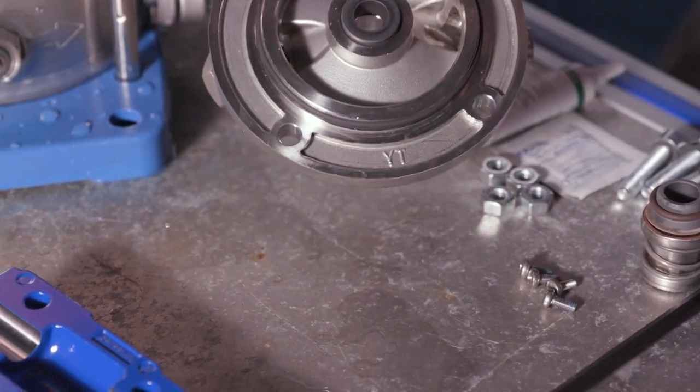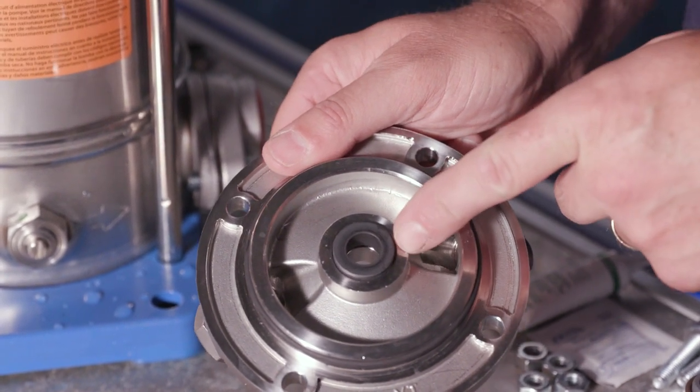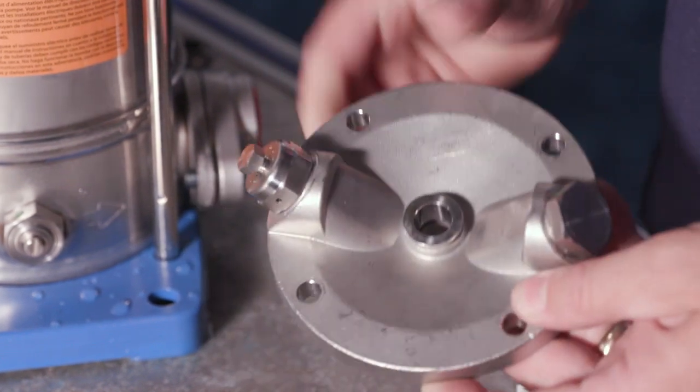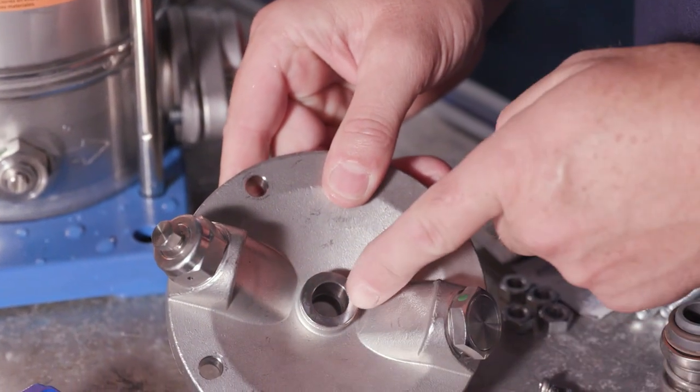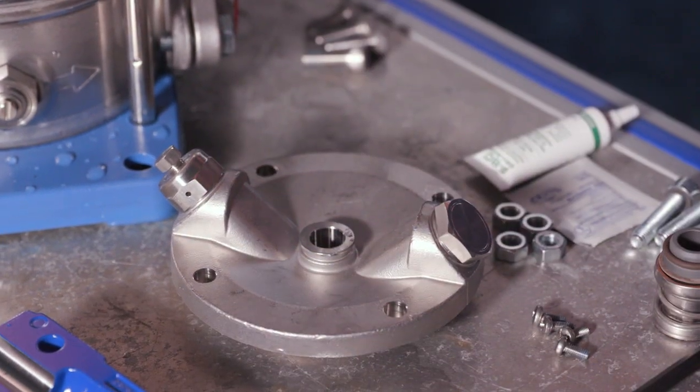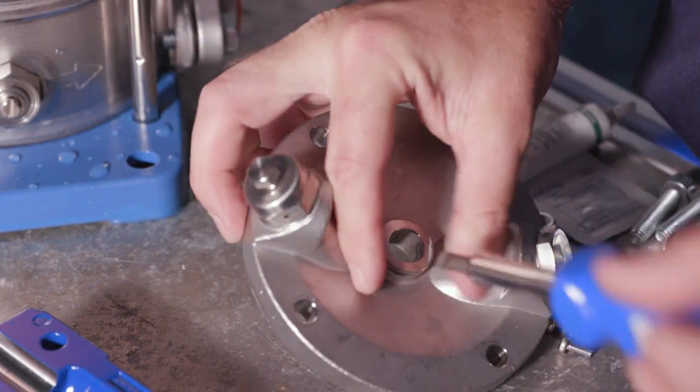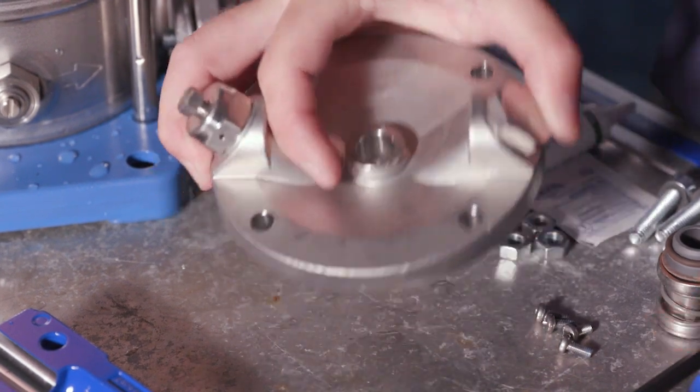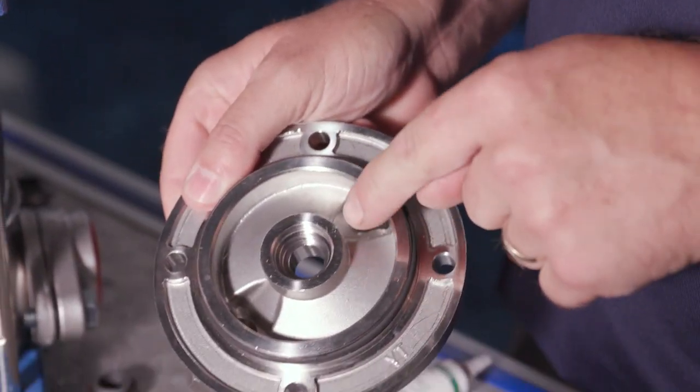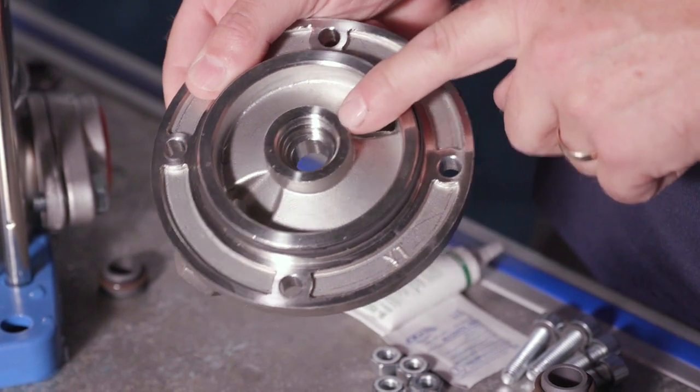We're going to install a new mechanical seal. The first thing that you want to do, notice that we didn't pop out that old mechanical seal stationary face. Easiest way to do that is just flip that over and pop that out from the back side. Now that we've got that popped out, we're going to install the stationary portion of the seal.